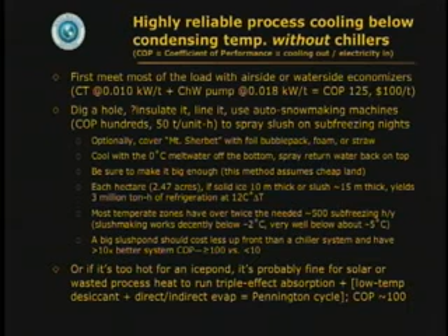You spray the return water back on top. You make it big enough, because you have cheap land in this site. And it turns out that each hectare will give you 3 million ton-hours of refrigeration at 12 Celsius, and most temperate zones have plenty of cold nights to do this with. And it's cheaper than a chiller system and well over 10 times as efficient. If it's too hot to do that, then probably you have good conditions for using solar or wasted process heat to run a stack of absorption and desiccant and evaporative cooling to get, again, about 100 units of cooling per unit of electricity. So again, less stuff to pump around. There's a lot of pumps and fans and stuff associated with cooling.